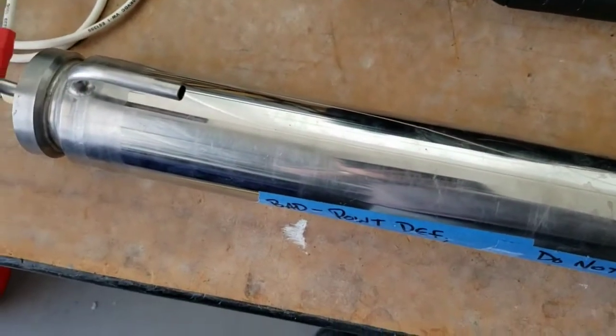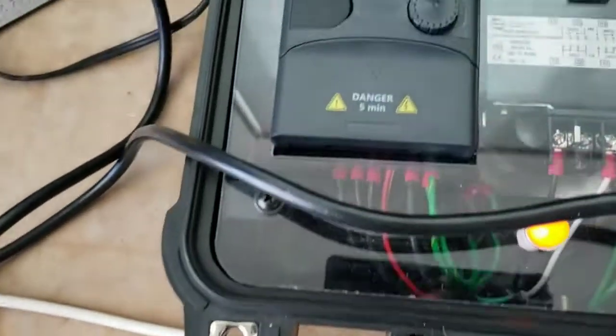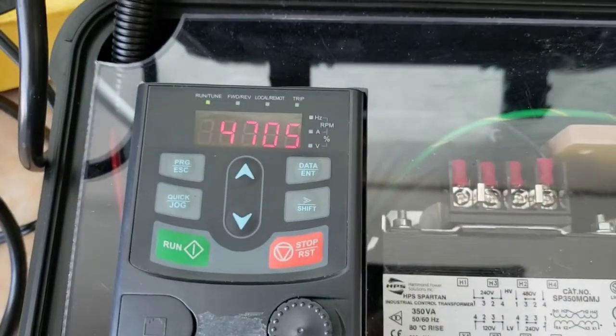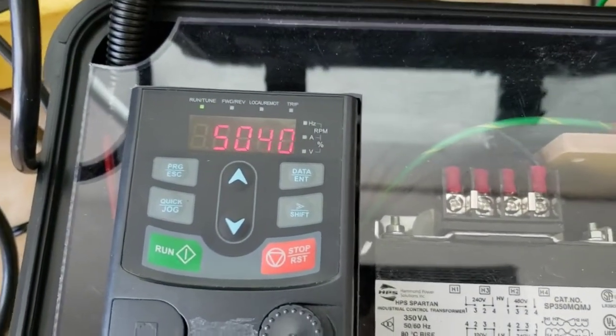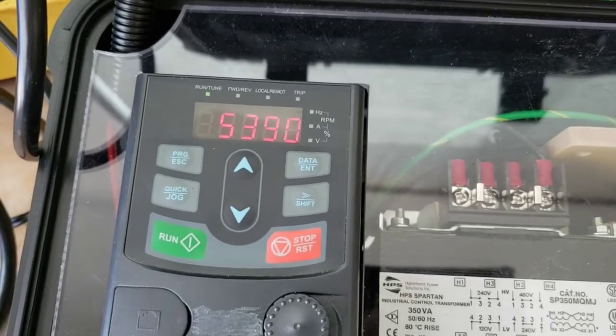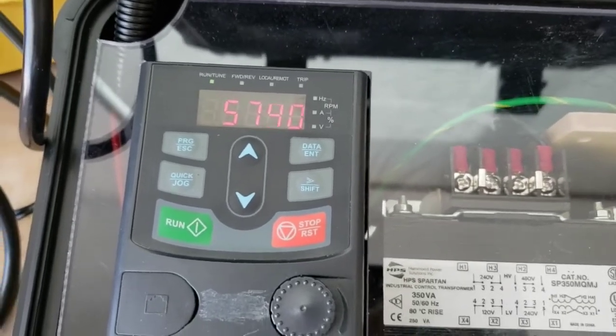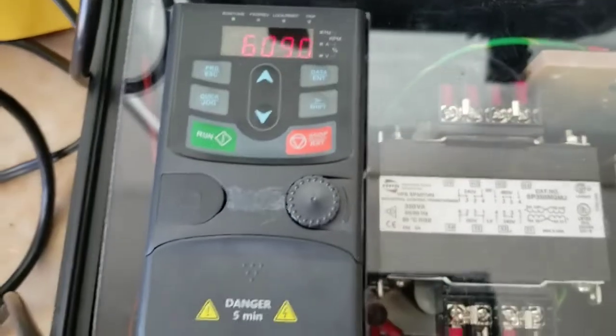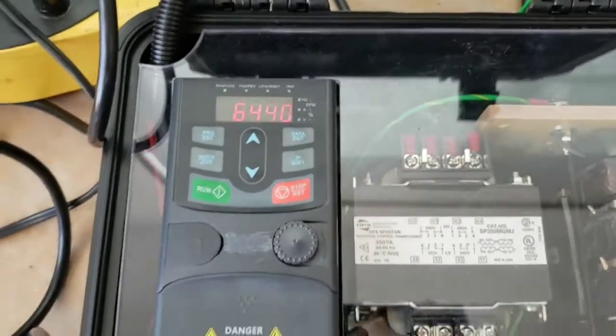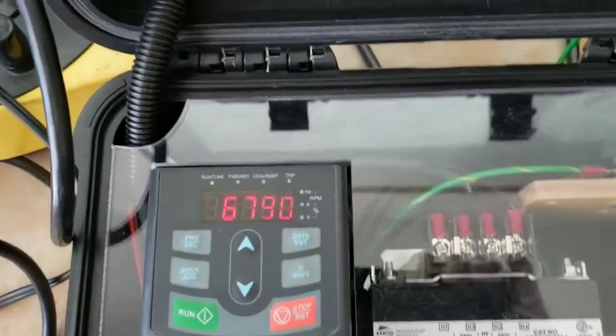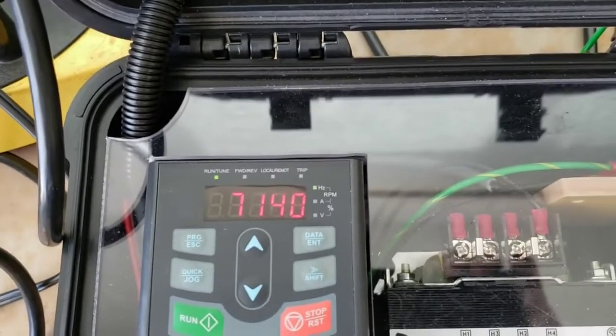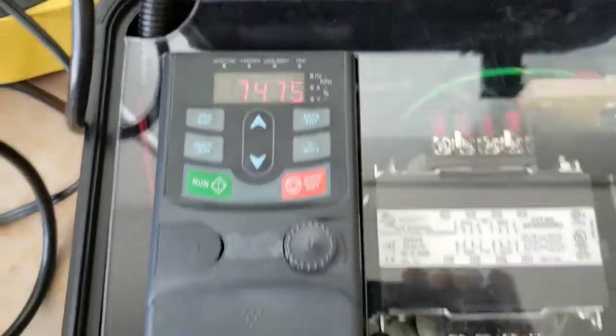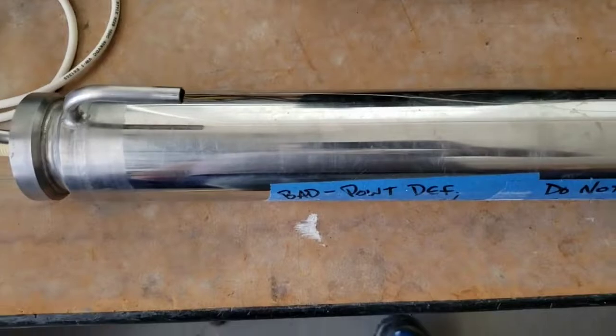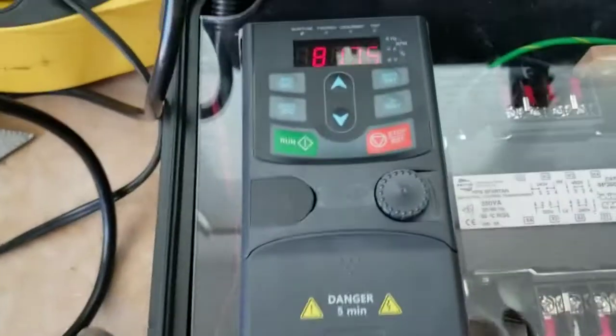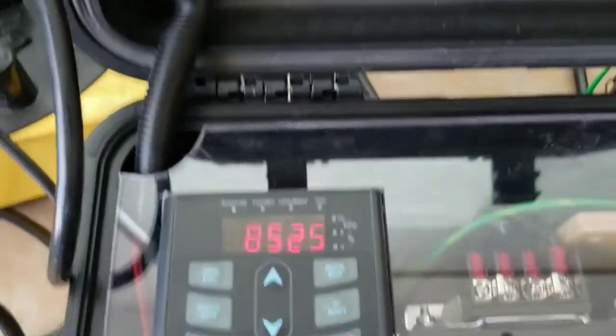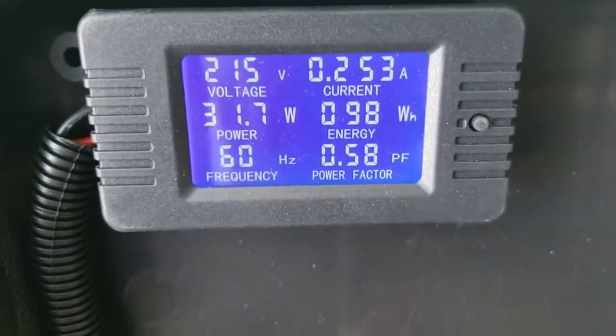At about 3,800 hertz, we're starting to hear it. Now we know there's kind of a dead band between 4,000 and 6,500 hertz. But once we get above 7,000, power's going to start kicking on again, and then we'll definitely hear it freaking out. There we go. Now we're getting our arcing. Wattage is falling down.